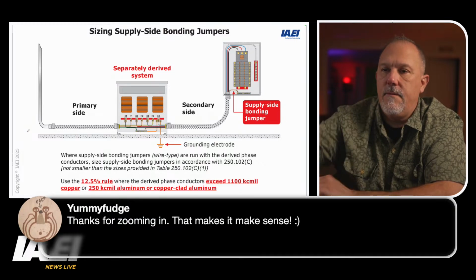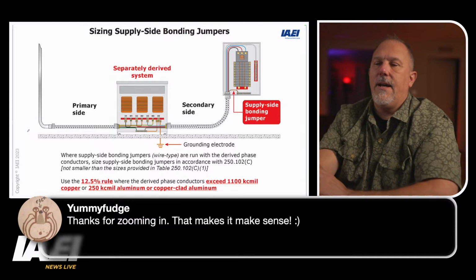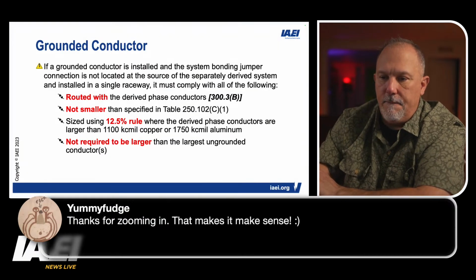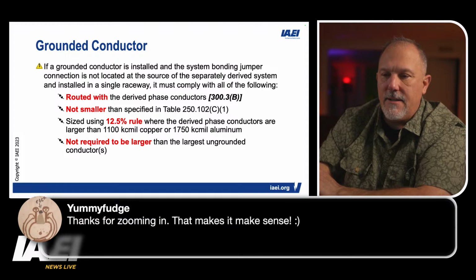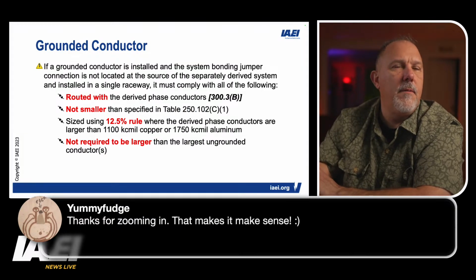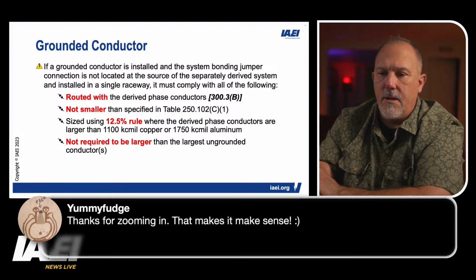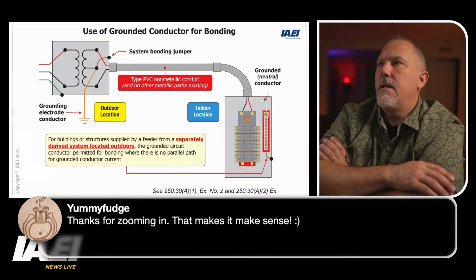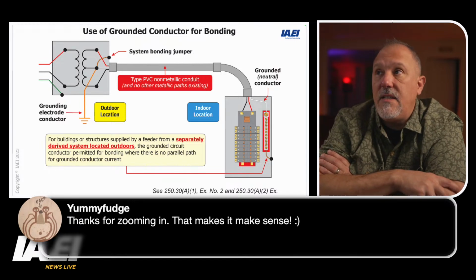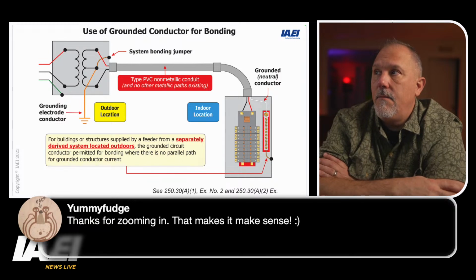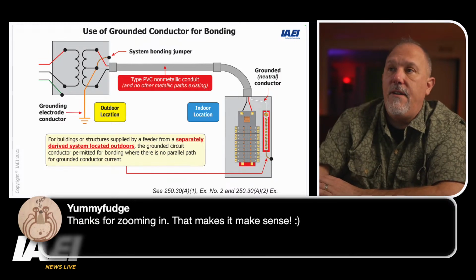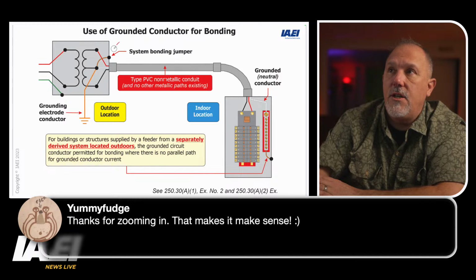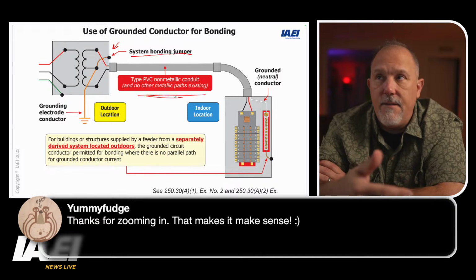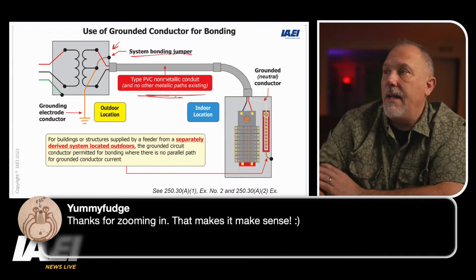I'm gonna move that down just a little, that way I can see the screen. All right, so we already talked about that. Now this is your type PVC non-metallic conduit. In this case, you have your grounding electrode and your system bonding jumper done up here. So there's your system bonding jumper. This is PVC, non-metallic, so we can't rely on that to bond both sides.